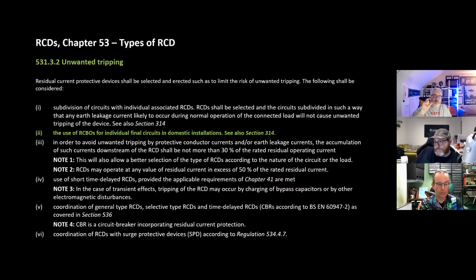And we will tell you why when we get into the testing part, because it's fairly evident that, given yesterday we agreed that they'd removed anything up to 10 milliamp needing any special measures, the dual earthing on the back of sockets is now gone. It's fairly evident they're not worried about anything up to 10 milliamp. Yeah, the high integrity earthing requirement for two connections is gone, and you can see it's now just pushing people down that RCBO line. Is this well worded? No. Can it be better?